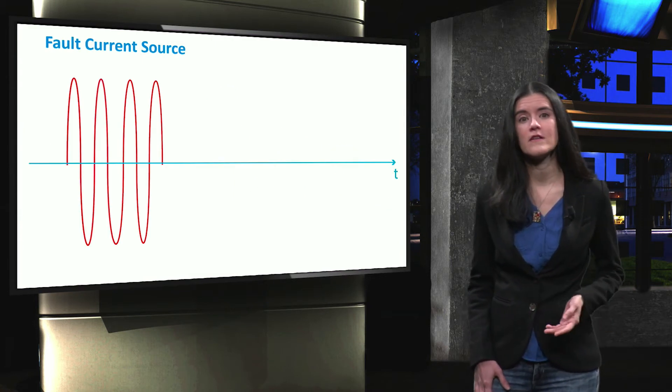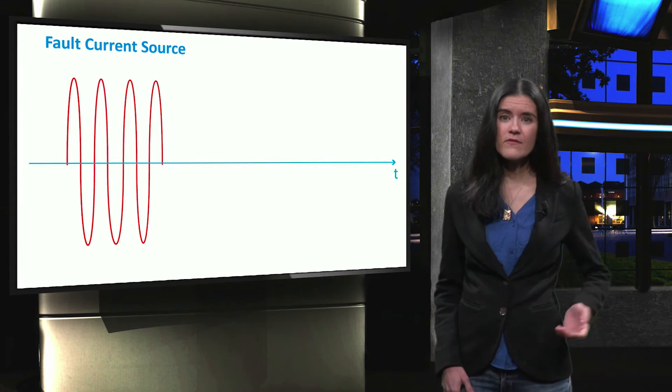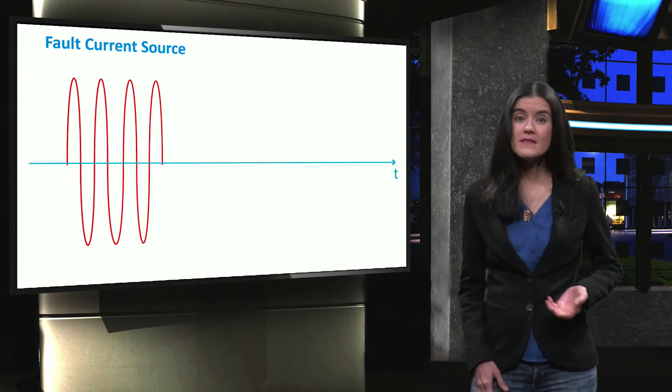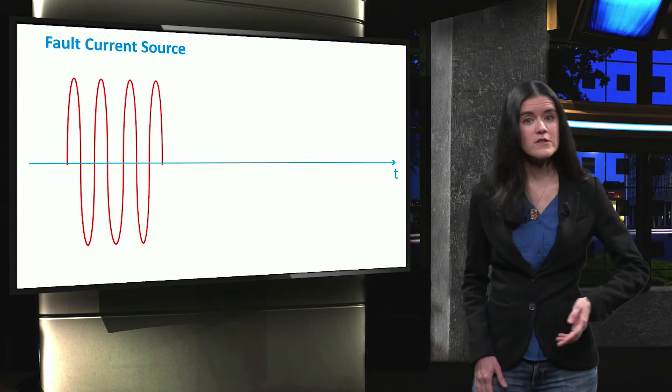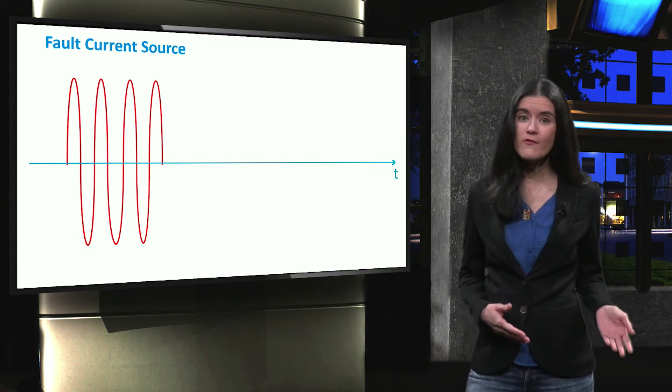As we have previously seen, short-circuit currents are relatively low in microgrids. This can affect the fault current sensitivity. One of the solutions for that problem is to connect a fault current source.